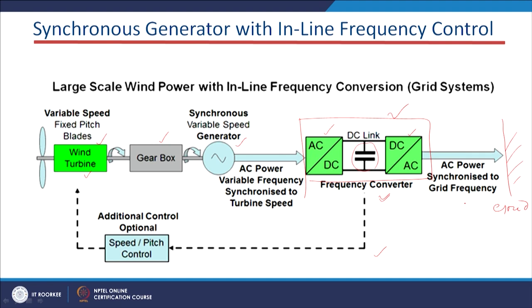In this block diagram, the electronic converters are connected between our wind energy system and the grid system. This is a large-scale wind power in-line frequency conversion system — it is 'in-line' because the total amount of power generated by the synchronous generator is fed to the grid through the power electronic converters. One hundred percent of the power flows through this converter section to reach the grid.